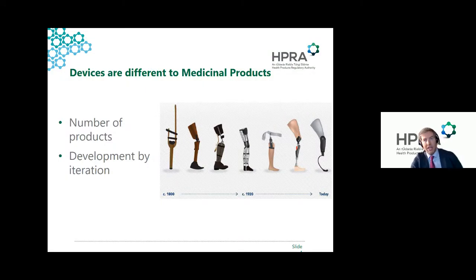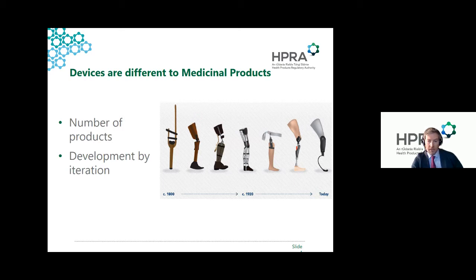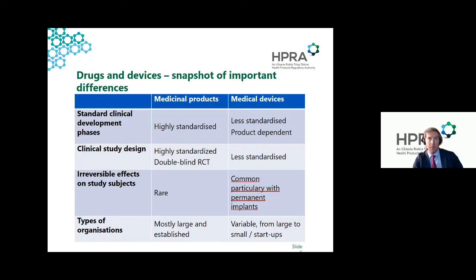When you consider medicinal products and medical devices in terms of the regulatory system, two things can be quite prominent. First, we have a huge number of medical devices in Europe — running into the hundreds of thousands — whereas drugs run to the tens of thousands. Second, iteration — making small changes to a product over time — happens routinely with medical devices and is far less prominent with medicinal products. This is an important consideration when we talk about the medical device lifecycle.